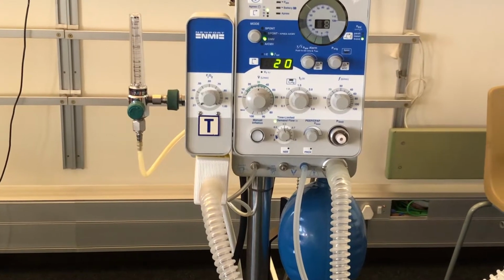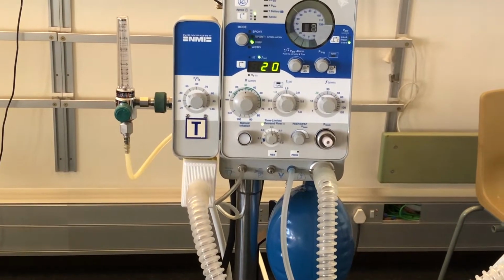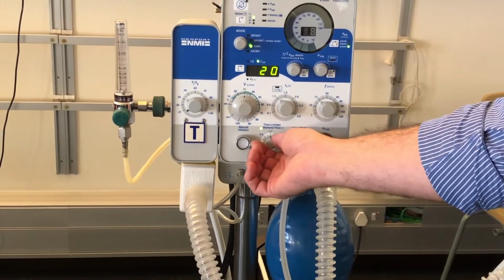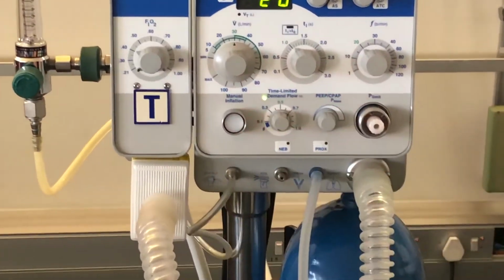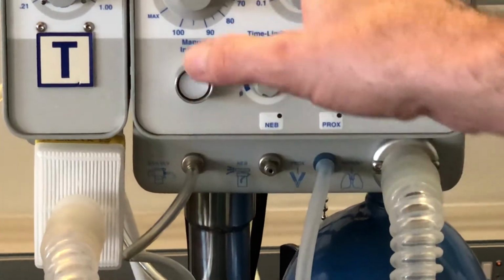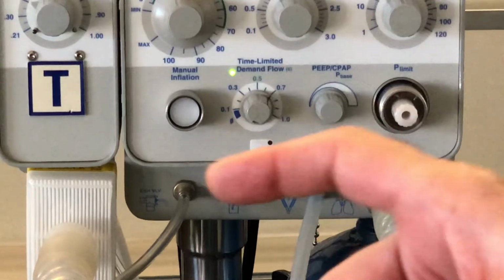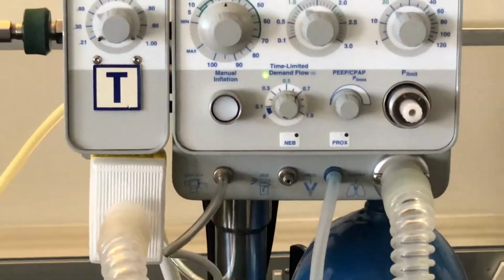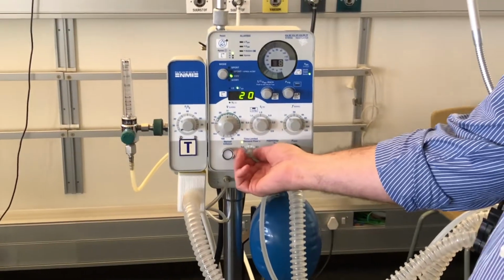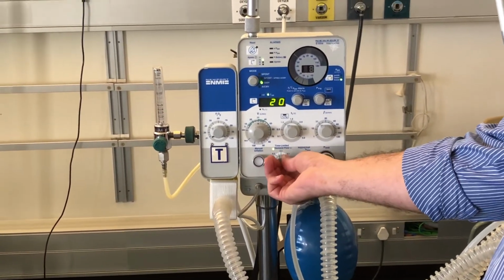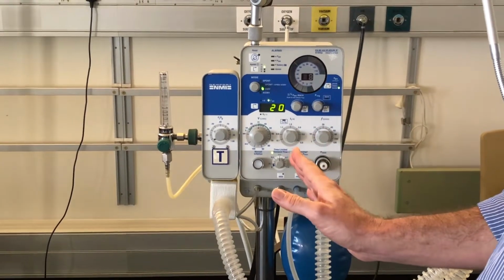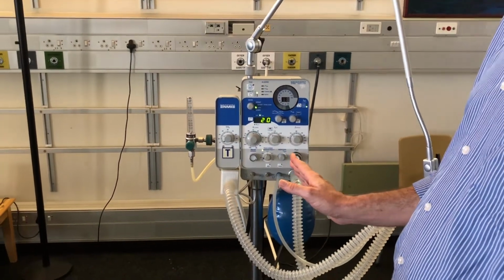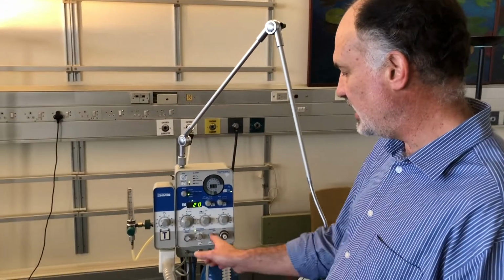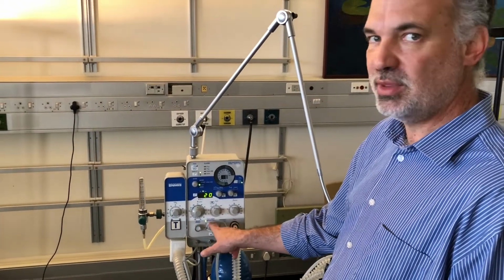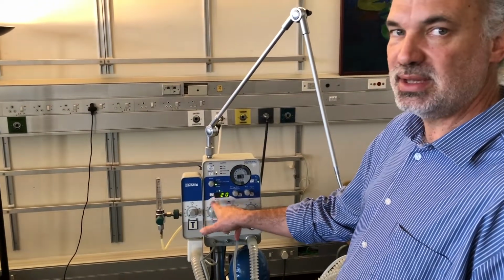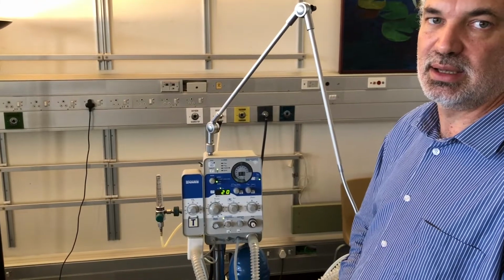But clearly, many patients may want to take an inspiration of more than a half a second's duration. If that were the case, you'd have to increase the setting to make the time that the ventilator will make the flow rate available to the patient approximately the same duration as the patient's respiration. And that we can obviously either increase or decrease away from the green setting that's given on the machine. And then just again to emphasize that in time-limited demand flow, the flow that the patient is going to get is the preset flow that we had on the ventilator.